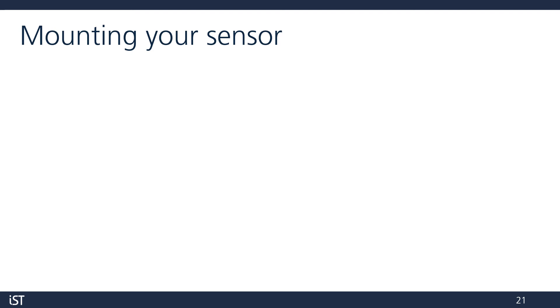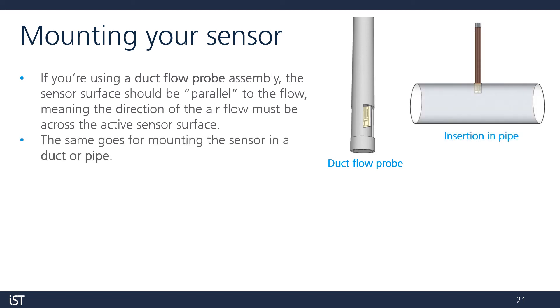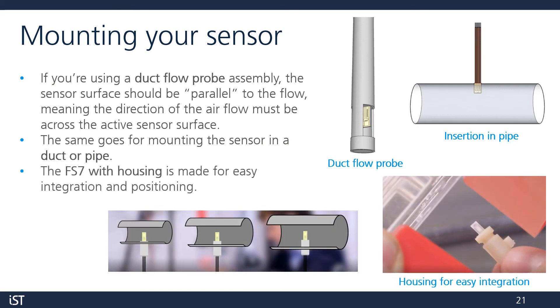We're often asked how the sensor should be mounted in the flow path. If you're using a duct flow probe, be sure the sensor surface is parallel with the flow, meaning the flowing gas passes smoothly over the active sensor surface. The same goes for a duct or pipe. One useful benefit of the FS7 with housing is a small tooth on the side — many customers add a notch in the hole they drill in their pipe, making it easy to position the sensor perfectly parallel with the flow.